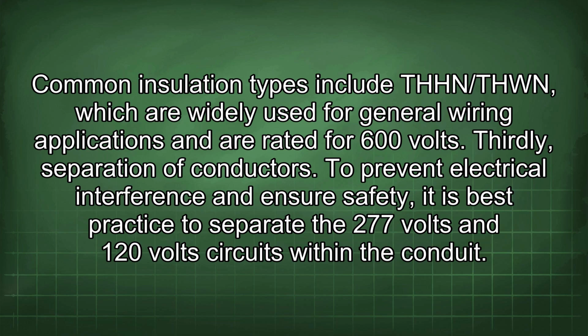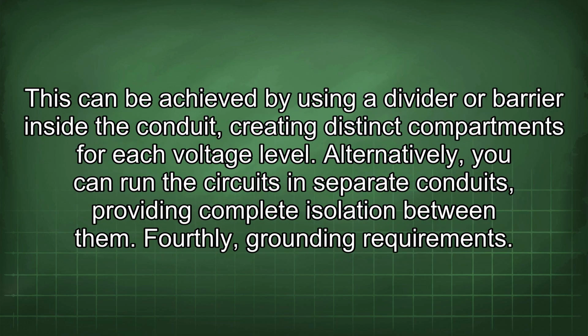Thirdly, separation of conductors. To prevent electrical interference and ensure safety, it is best practice to separate the 277 volt and 120 volt circuits within the conduit. This can be achieved by using a divider or barrier inside the conduit, creating distinct compartments for each voltage level. Alternatively, you can run the circuits in separate conduits, providing complete isolation between them.